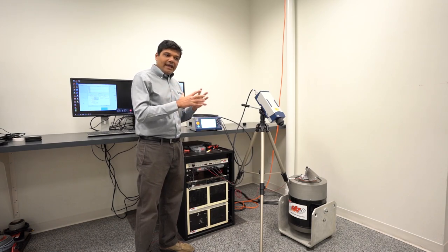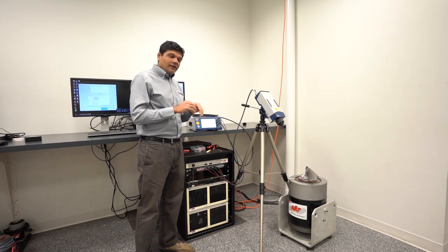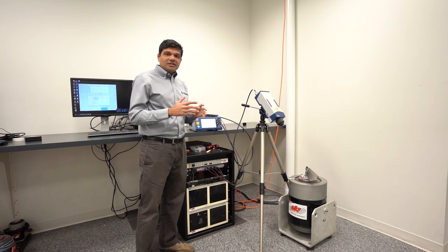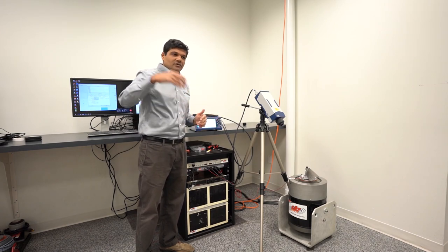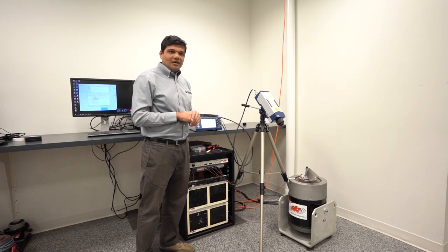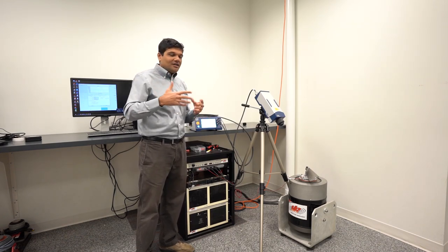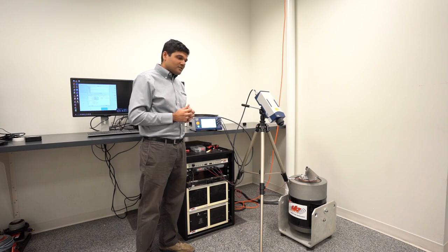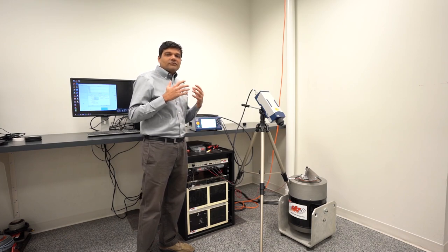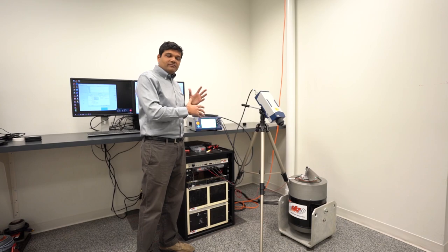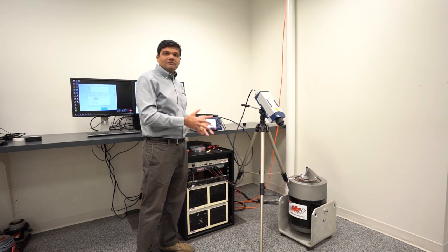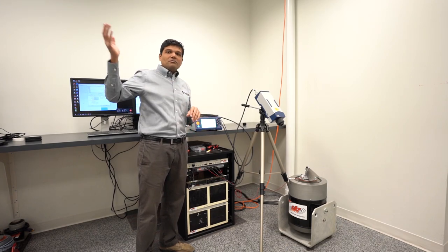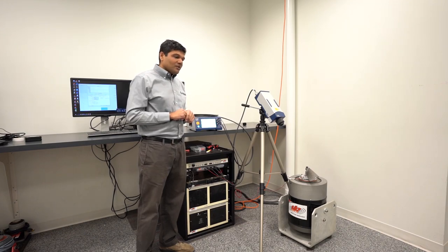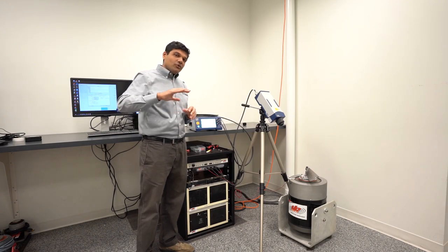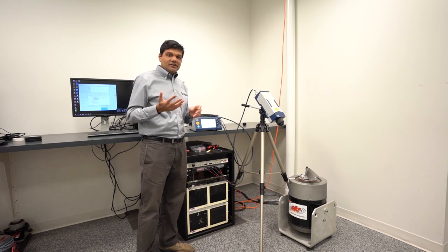Fundamentally, in terms of amplitudes and frequencies, a vibrometer is capable of measuring all the way from DC to several inches, theoretically several feet, but you might lose focus after some point. In terms of frequencies, it goes all the way from DC to several megahertz. Vibrometers these days are capable of going all the way up to 2.5 gigahertz in frequencies for some applications.